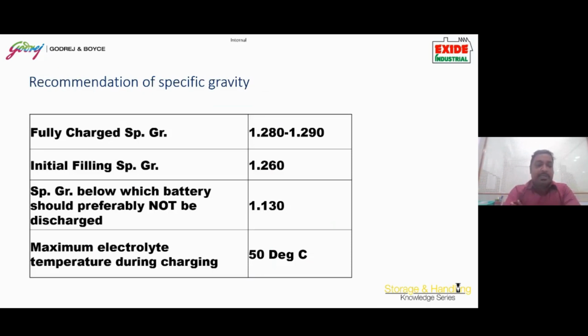And about the recommendation of specific gravity: we can measure the state of charge of the battery by just measuring the specific gravity also. As I said earlier, the fully charged battery will always have a specific gravity from 1.280 to 1.290. We call this state of charge 100% SOC, 100% state of charge. And the initial filling specific gravity, when we commission the batteries, is from 1.250 to 1.260.